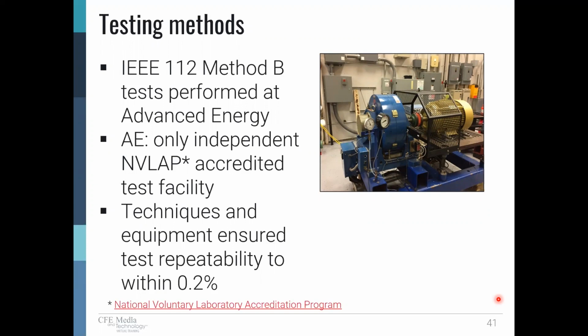NVLAP is the National Voluntary Laboratory Accreditation Program. And when we say independent, what makes them independent is that simply they are independent. They stand alone. What's not independent would be the motor manufacturers themselves. The motor manufacturer builds the product. They have accredited labs that they can go back to the Department of Energy and say, we've tested this in our lab, and it is as efficient as we're showing on the nameplate. It meets the Department of Energy requirements.